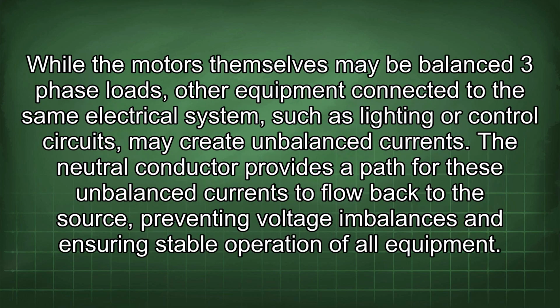While the motors themselves may be balanced 3-phase loads, other equipment connected to the same electrical system, such as lighting or control circuits, may create unbalanced currents. The neutral conductor provides a path for these unbalanced currents to flow back to the source, preventing voltage imbalances and ensuring stable operation of all equipment.